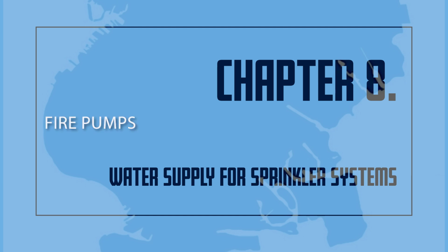Fire pumps. Fire pumps can be used as a main water supply source for sprinkler systems. They may also be used in combination with gravity tanks to supply sprinkler systems. Fire pumps are designed to take the water from a supply source and then discharge the water into the fire protection system under pressure. The amount of pressure with which the water is discharged from the pump is called the total head. The total head is measured in pounds per square inch. The higher the PSI rating of the pump, the greater the pressure with which the water can be discharged. Fire pumps shall be sized to satisfy the hydraulic requirements of the sprinkler system.